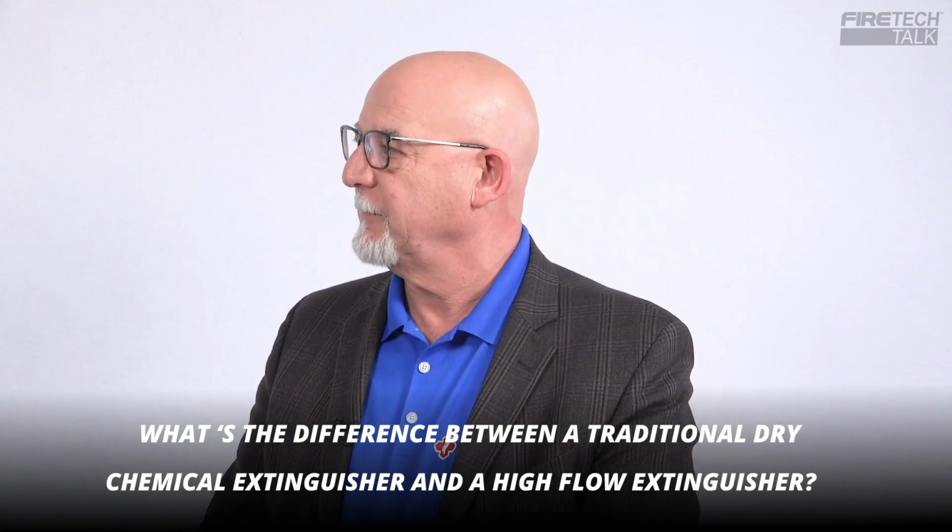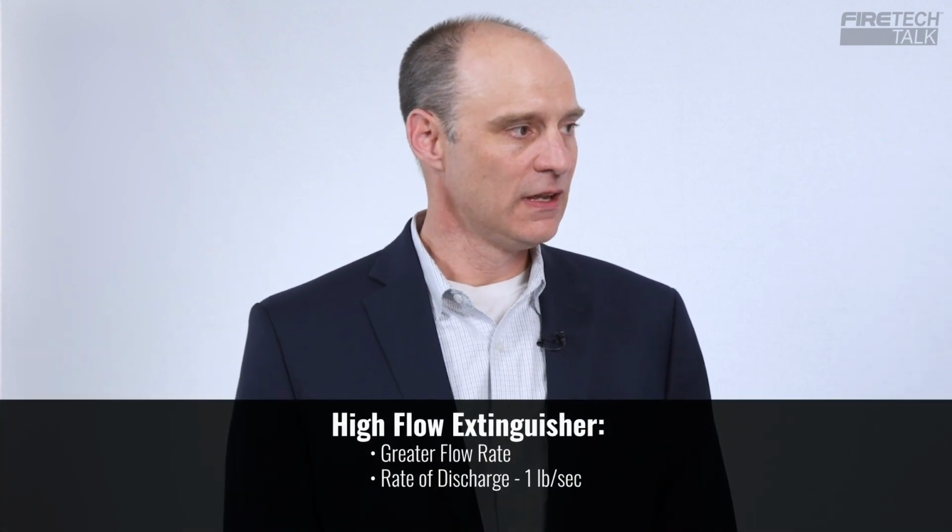What's the difference between a traditional dry chemical extinguisher and a high-flow extinguisher? A high-flow extinguisher has a greater flow rate, so by NFPA 10, it's 1 pound per second or more. 1 pound per second? Yes. Sounds like a lot of chemical. Yeah, it's a lot of chemical, and it makes it a whole lot easier to extinguish fires like obstacle fires or three-dimensional fires.